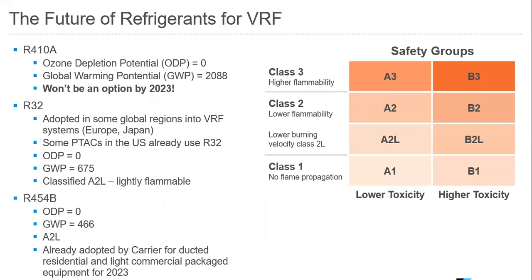So what is the future of refrigerants for VRF? What we see happening is that R410A will go away, won't be an option by 2023, which is less than 3 years from now. Many manufacturers are going to move to R32, which is a refrigerant actually created by Daikin, and the patent was opened to allow other manufacturers to use it. And R32 has already been globally adopted in many VRF systems in Europe and Japan, including some PTACs that are already being manufactured and used in the United States. The advantage of R32 is that the ozone depletion level is 0, and the global warming potential is lower than that of R410A by a factor of more than 3.